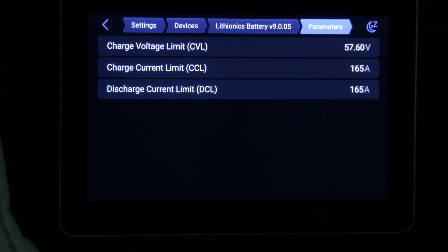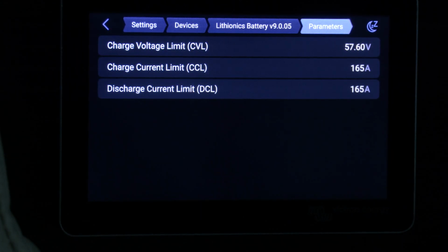As that battery gets to full, or maybe it gets over temperature or under temperature, it's going to reduce those thresholds to keep the battery safe. This is one of the great things about the system: if the battery's approaching full, it says, no, I don't want 165 amps anymore, I just want 3 amps to top it off. These numbers will change and be communicated out to all of the charging devices to keep the battery safe and ensure long life.